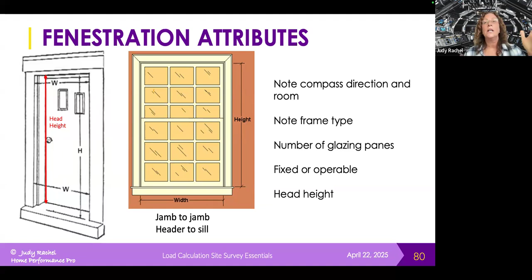Internal shade devices and bug screens make a difference for the building load, so it's important to describe and quantify them. We look at how an internal shade device or sunscreen would be used at our design conditions, which is basically a hot day around 5 p.m. in July, when a design day typically happens.